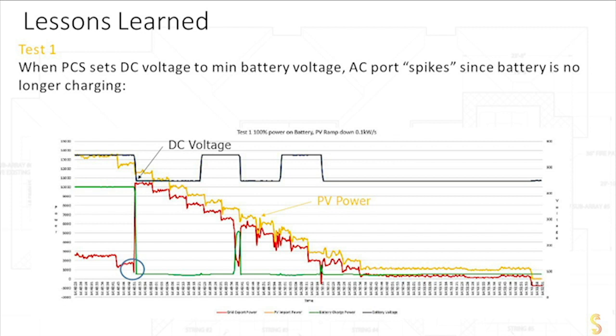And what does that do? When you drop the voltage down on the battery, the red line skyrockets back up. It spikes because there's no battery charging. The battery's not taking any energy away from the solar curve. So the battery is now off. So all that solar power is now going out into the grid.